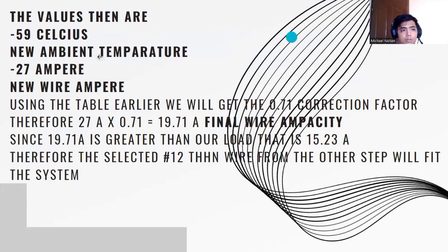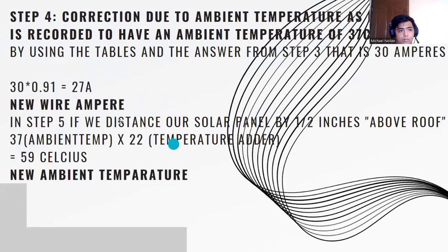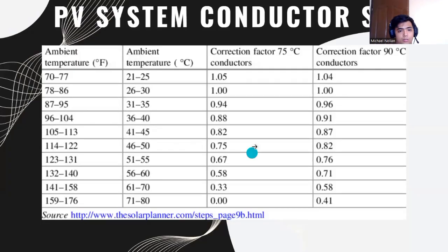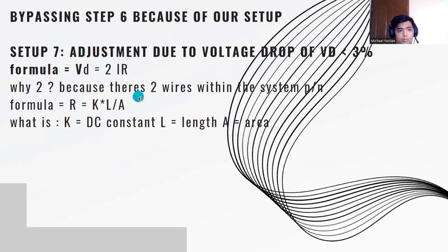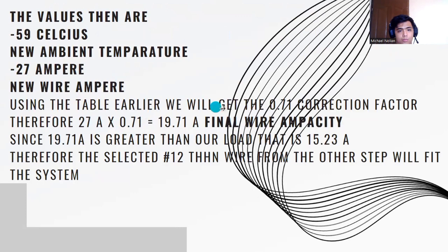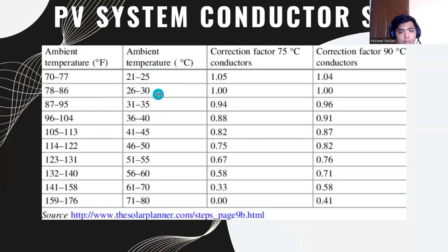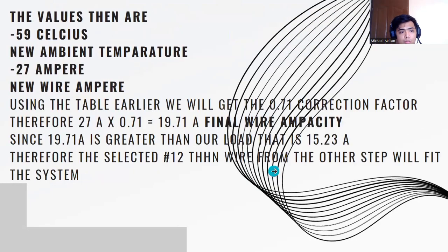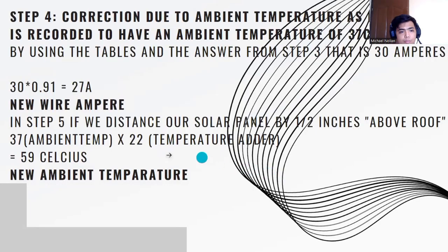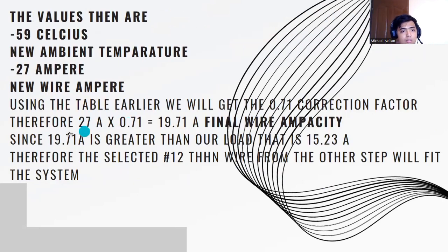Next. So our values: 59 Celsius is the ambient temperature. Okay, I think it is reversed. No, 59 is the ambient temperature, 27. Yeah, sorry. So using the table earlier, we get the 0.71 correction factor. Let's see again, 27 or 59. From that table, we get the 0.71, from 27. Here. There it is, 56 from 59. That is where it comes from.